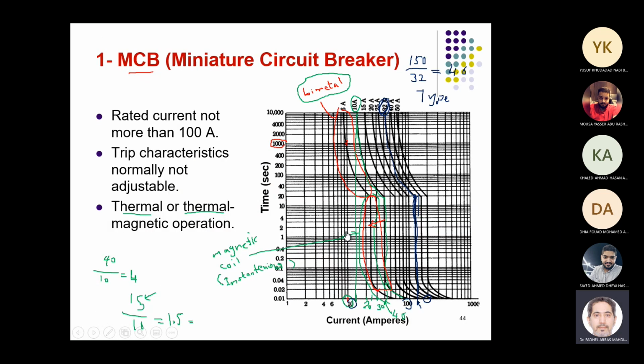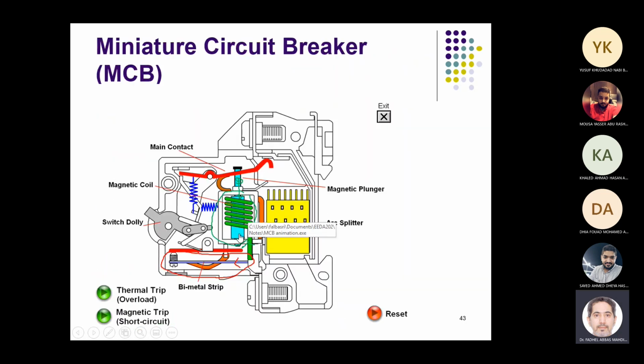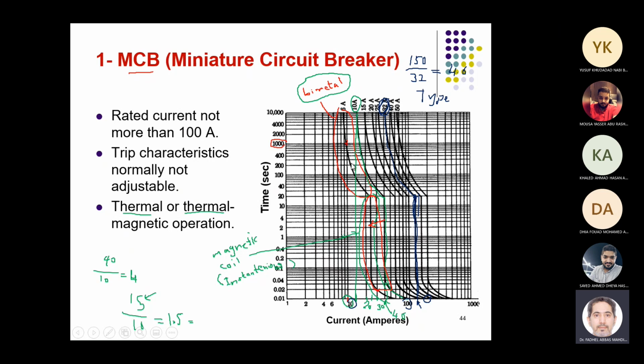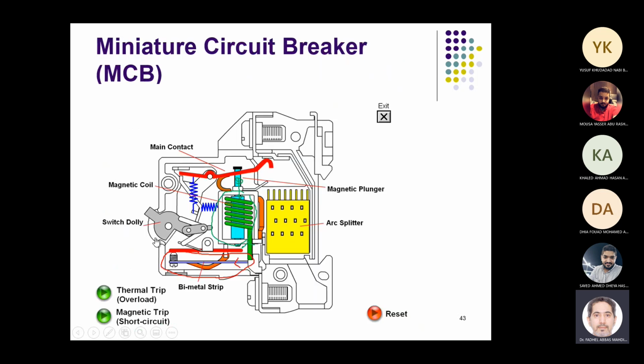So the curves, if you would like to see the tripping characteristic of this element plus this, they constitute this. So this is for the overload element, which is the bimetal element, and this is for the instantaneous. It's like a relay characteristic. We have instantaneous plus time overcurrent, like the 51 elements, and this is the instantaneous. So this is acting like the 50 instantaneous elements, and this is the time delayed element.